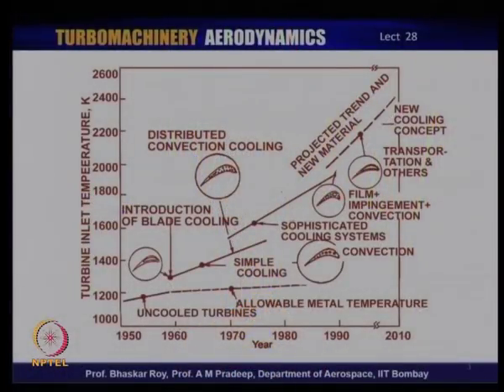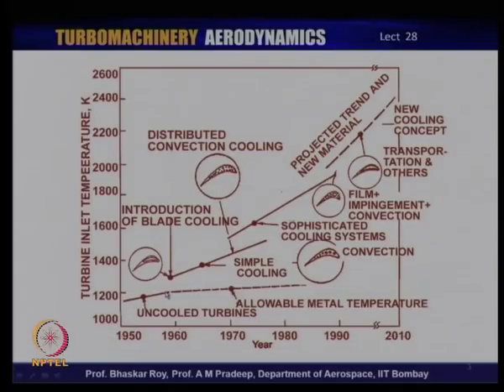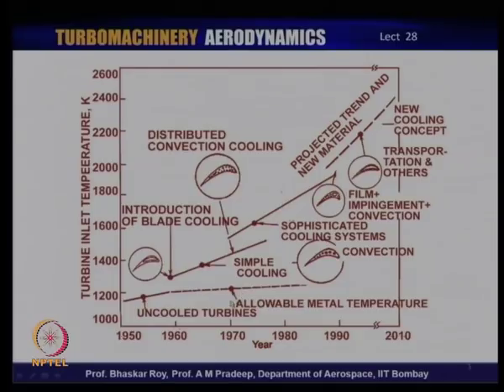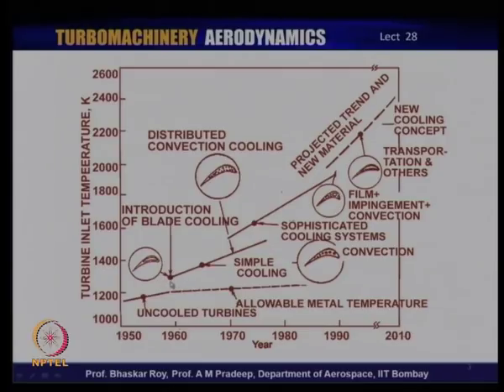Looking at the graph available in many books, in the early era of the 1950s, most blades were actually uncooled blades that could take up to about 1000 degrees centigrade. From there onwards, if aspiring towards higher turbine entry temperature, you have to resort to some kind of cooling technology. A simple cooling technology was used in which certain cold air was passed through the blade, providing about 25–30 degrees of cooling to begin with, which was sufficient to raise the temperature by about 50 degrees. Slowly the temperature started rising as the cooling technology improved.